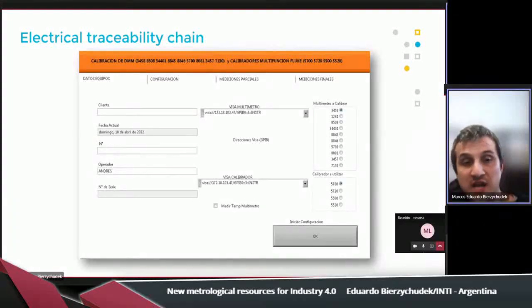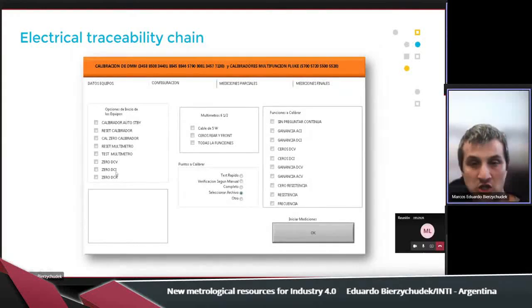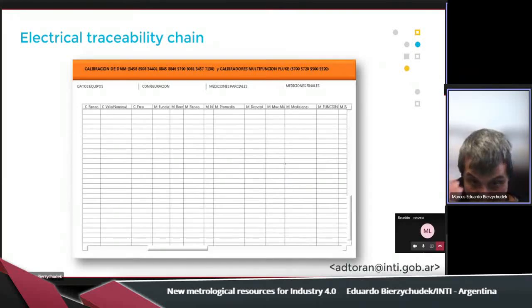So the board will be integrated to a software. This is a software that is actually used to calibrate this type of instrument, and it was already updated to control the multiplexer by USB port. You select the instrument to be calibrated and the calibrator. You can select the address of both instruments and put some information about the service itself. Then you can select what type of service you are interested in doing. And finally, you run the program and you start to see all the information in this spreadsheet.